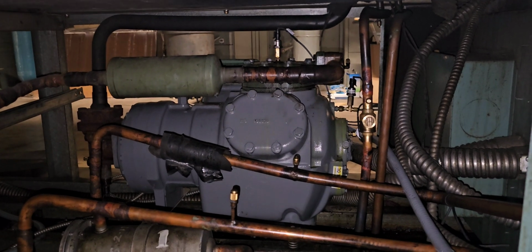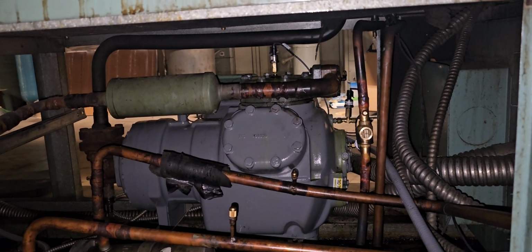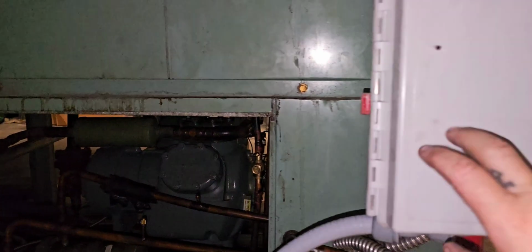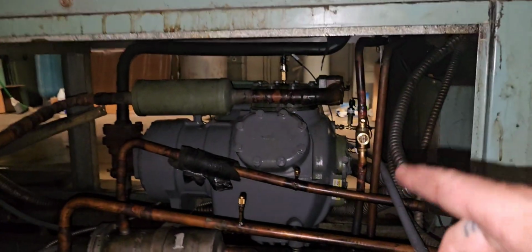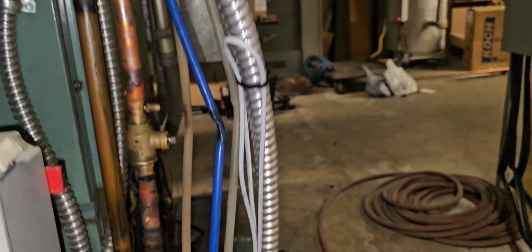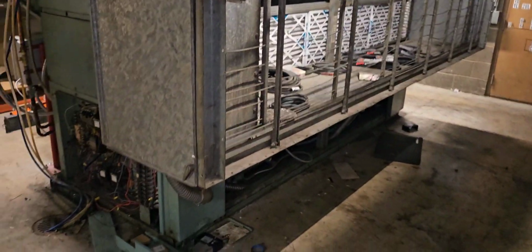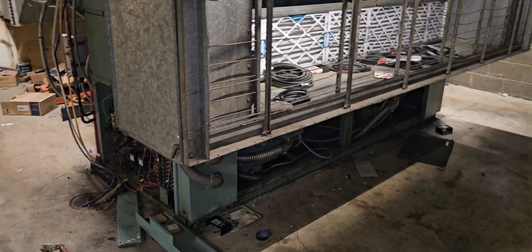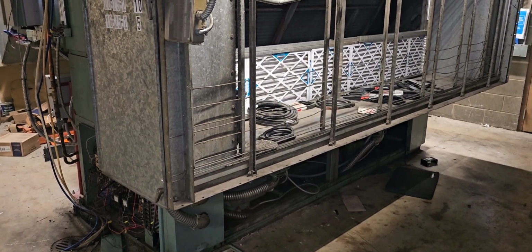If for some reason the pressure gets too high or too low, then those relays that are inside here open up and kill that compressor, just like my compressor safeties. So that's what I keep saying: this is just like running a normal safety circuit, but instead of using mechanical controls like dual pressure control and oil controls, I'm just using a board and ROs and AIs.